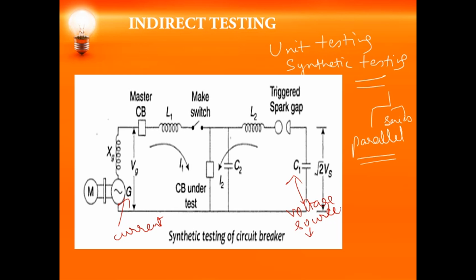This provides the recovery voltage, and the controlling of that is done by L2 and C2. In order to apply it, you have a triggered spark gap. By applying this high voltage and high current, you see how the circuit breaker under test is going to perform. If the circuit breaker under test fails to operate, then the master circuit breaker has to operate. So this is overall the testing of circuit breakers. The main tests are the routine test and the type test. They can be carried out either directly or indirectly, in the field in a real-time situation, or you can install a laboratory setup so that you can try to get the practical voltage, whatever is possible. So this is all about the operating mechanism and the testing of circuit breakers.